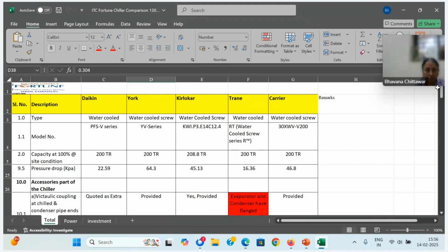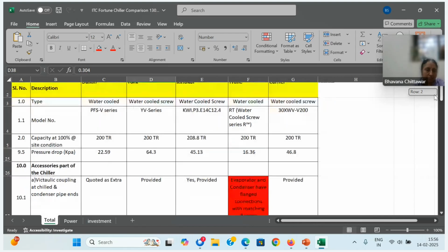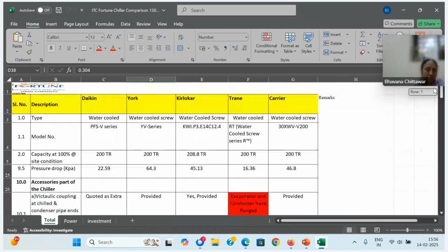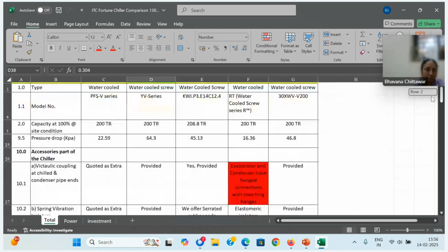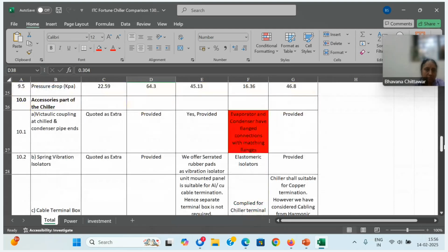This is one classic case I'll just show you. This is not a compressor. This is a chiller. The chiller's original design was 280 TR. So I calculated that only 200 TR is sufficient. So straight away the investment has come down. Again, for 200 TR, there are 5 suppliers. So all have given various parameters as may be required.